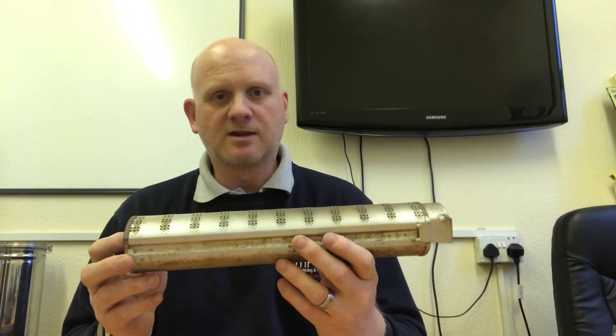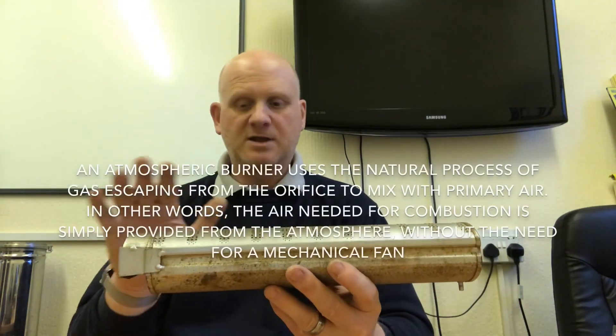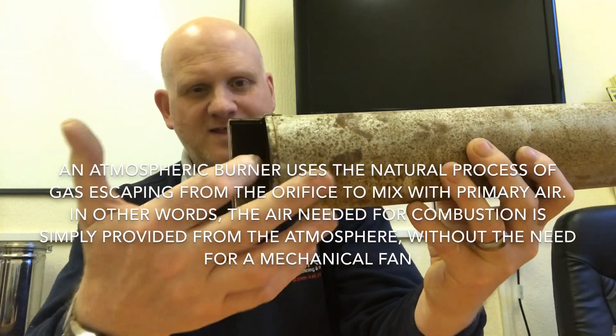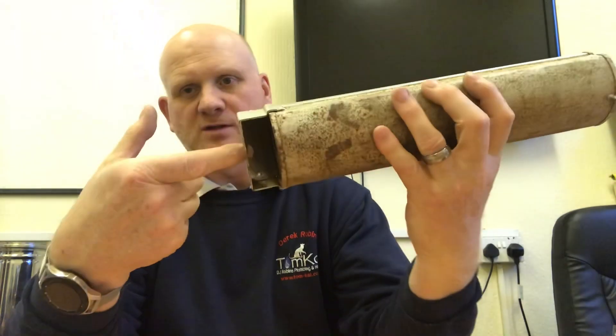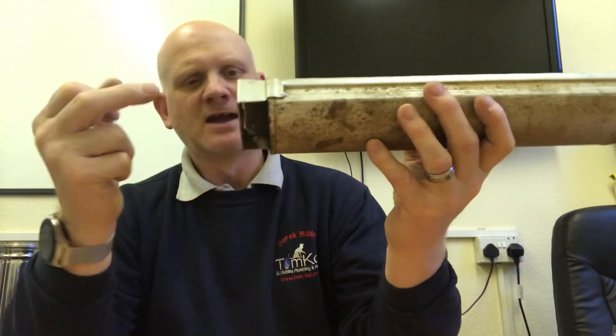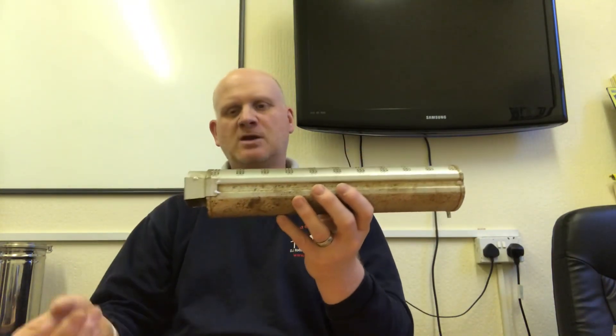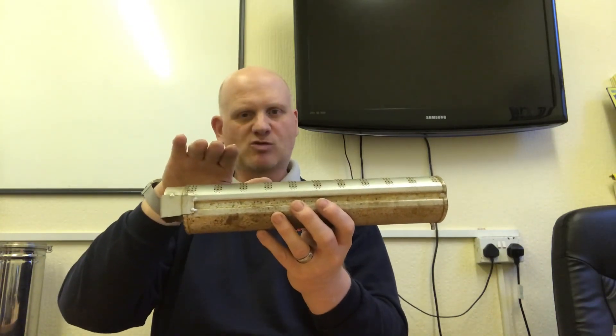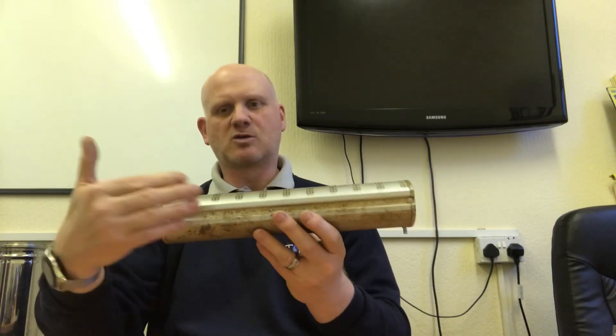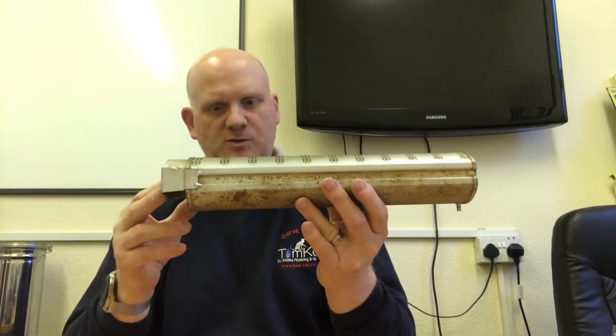This is what the burner was in the back boiler or the floor-standing boiler — this is what we call an atmospheric burner, meaning the gas would be burned upwards under atmospheric conditions. This hole here is where the pre-air would come in for combustion. The injector from the gas valve would inject the gas in, mix with the air, and burn across the burner. The burner pressure determined the flame height and kilowatts. There could be a bank of two, three, or even four of these depending on the boiler size.